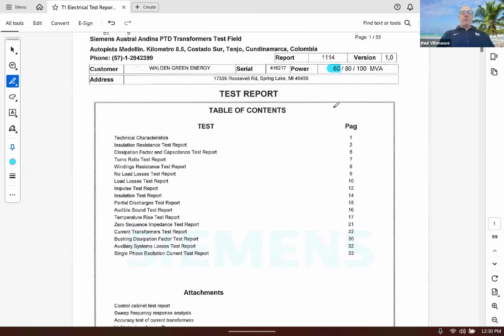Most transformers are rated on a base rating. That's what their impedances are, primarily because that's what we know it's going to operate at. It may or may not operate at 80 or 100. It just depends on temperature and loading. So that's the first important part.